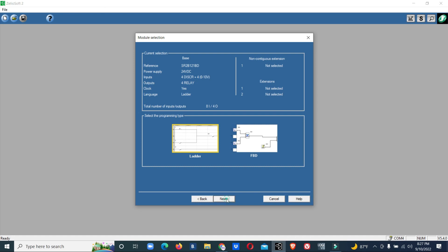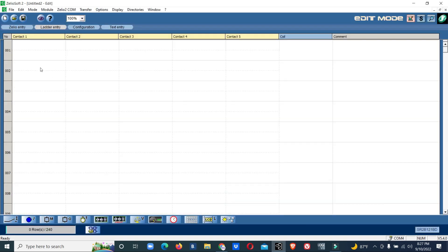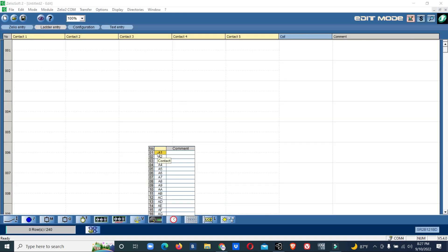Now the logic is: the pump will start if the pressure reaches 3 bar or below, and it will run till 5 bar. Once the pressure reaches 5 bar, the pump will stop. Then the pump will start again when the pressure drops to 3 or below. This is the logic we are going to make.